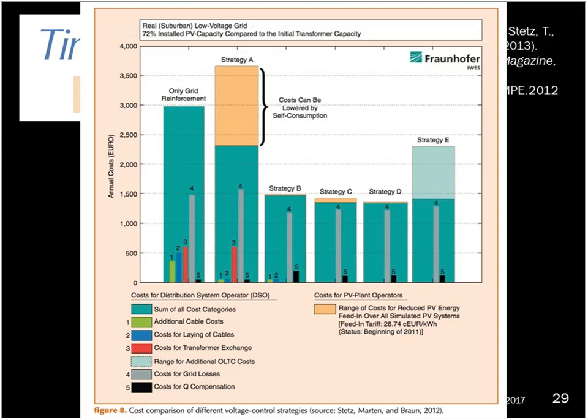And there's a similar study that I don't have cited directly here, but maybe I can have Brett email it out. It looked at California, and they did a big modeling study using data from PG&E and SolarCity, and they found that by increasing the number of transformer tap change operations, PG&E could get to about 100% solar penetration. That's measured based on the nameplate capacity of all the solar panels divided by the utility's median peak load. It's kind of confusing, but basically a lot of solar, and the increase in cost from the transformer tap changing operations was a vanishingly small part of the utility's total operation and maintenance budget. So they're not free, but they're relatively economical ways to change the way the grid operates in order to integrate solar.